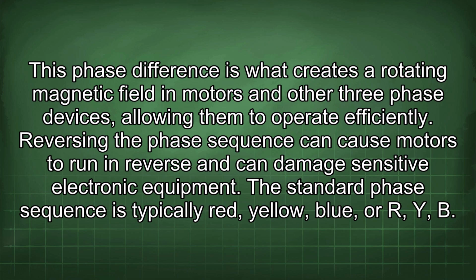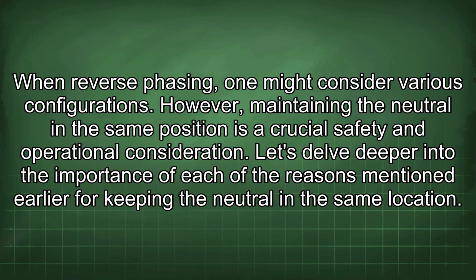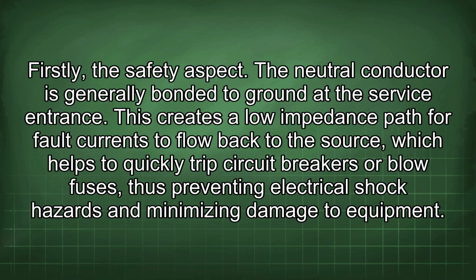The standard phase sequence is typically red, yellow, blue, or R, Y, B. When reverse phasing, one might consider various configurations. However, maintaining the neutral in the same position is a crucial safety and operational consideration. Let's delve deeper into the importance of each of the reasons mentioned earlier for keeping the neutral in the same location. Firstly, the safety aspect.